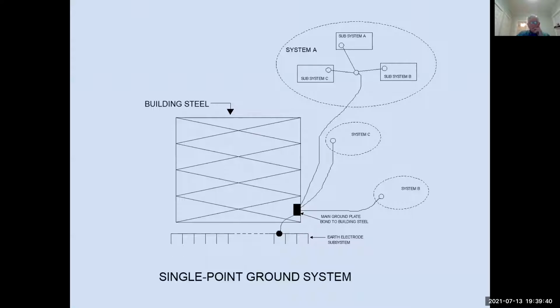I've used this before mainly for buildings, but it applies because many people in apartments say, well, how can I have a single point ground? The theory is you can have it grouped into adjacent equipment. So here's system A, you have several pieces of equipment or other systems, but then they all tie together, and then it all goes down from all these other systems to a main ground plate, which then gets connected to the earth electrode system. Incidentally, a building frame, a metal frame, is considered an extension of the ground electrode conductor. So you can use that to tie things together if you're in a building with that construction or an office building.